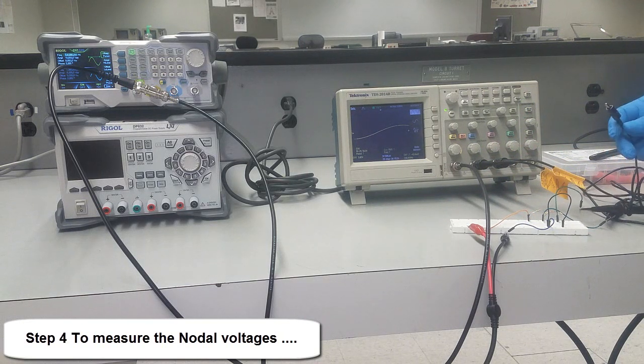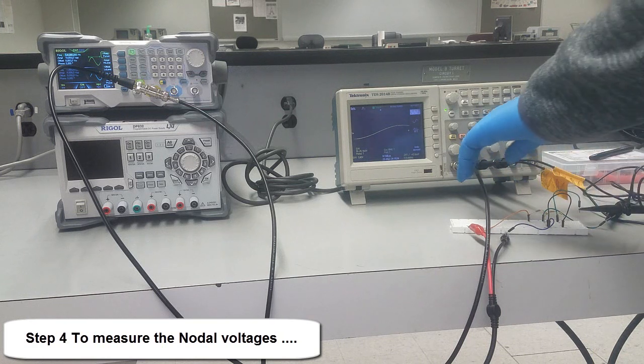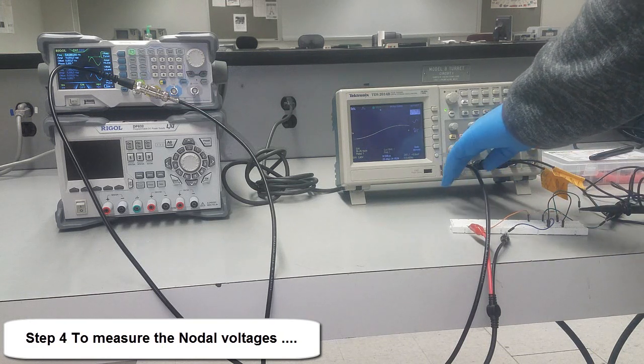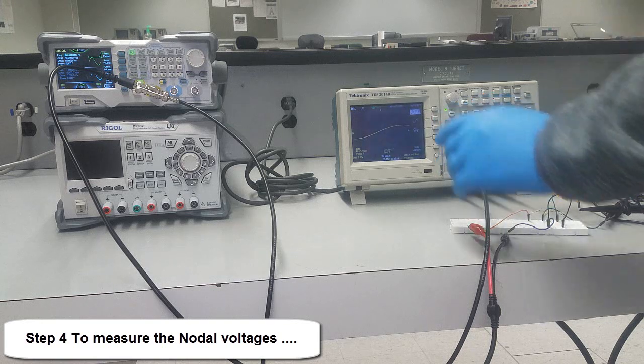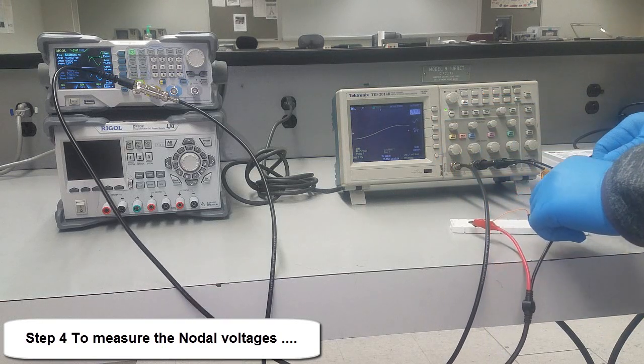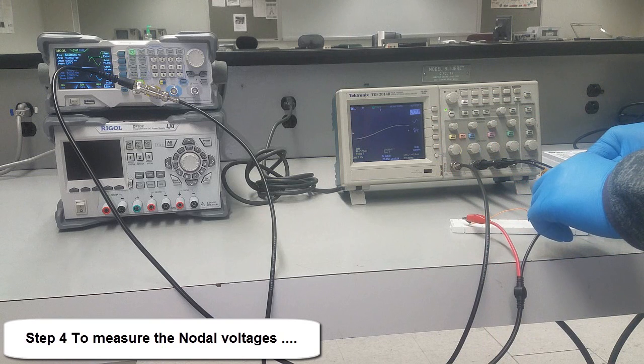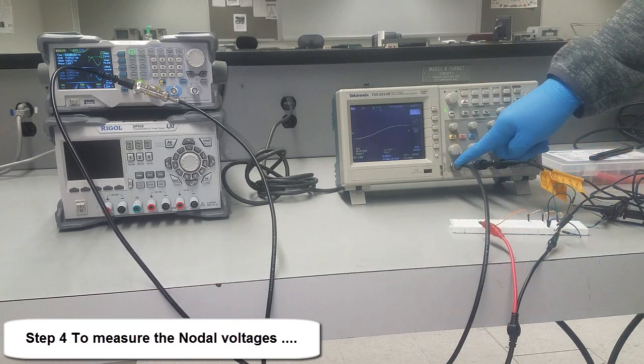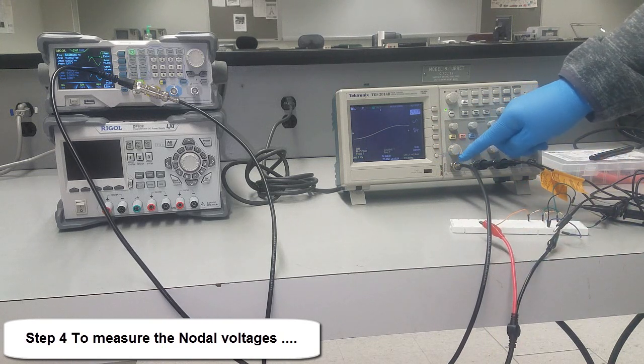Here I have a ground. So what happened is once one connector, one of those channels is grounded, all the channels are going to have the same ground. But I'm going to do it here as a form of redundancy. I don't need to do that. Once you ground one channel, all of them are going to have the same ground as this channel.